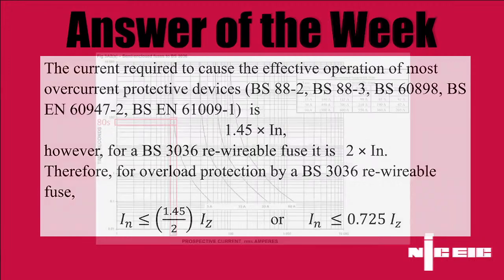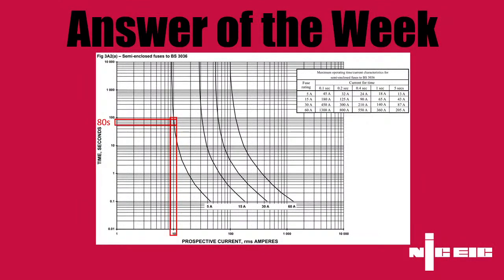Yeah, but what it boils down to is, we'll just very quickly show you. These are the time curves for 3036 fuses, and you can see that for our 5 amp fuse, even with a fault current of 10 amps, i.e. twice the rated value, it's taking something like 80 seconds for that fuse to operate. And the top of those curves is approximately at twice the In rating. That's the current needed to actually cause the fuses to operate.